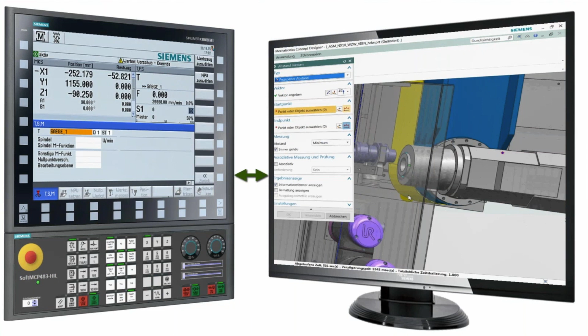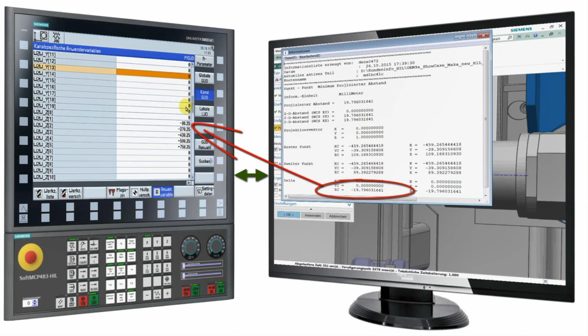Well, I can stop my simulation and actually take some measurements. So I'm going to take a quick measurement here. I can see I'm almost 20 mils off. I can go to the HMI, change my code through the HMI, put in the new value, and run it again, and you can see it lines up.